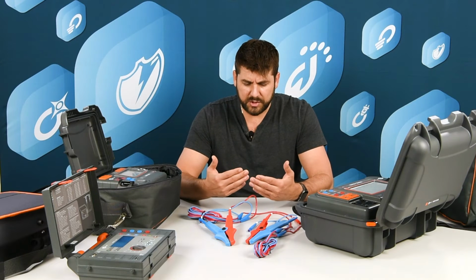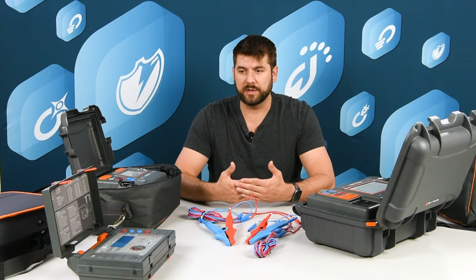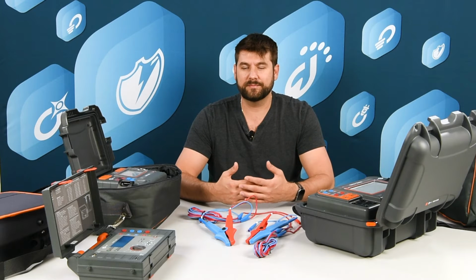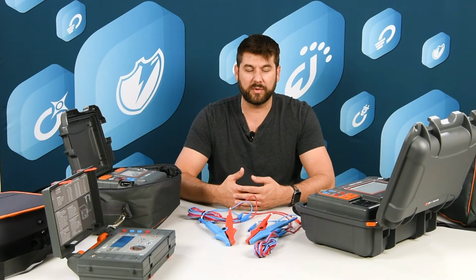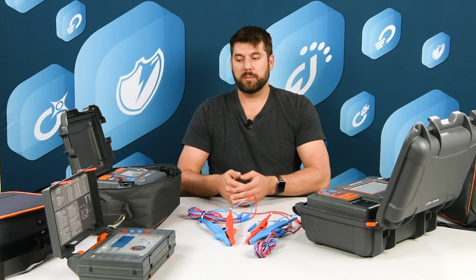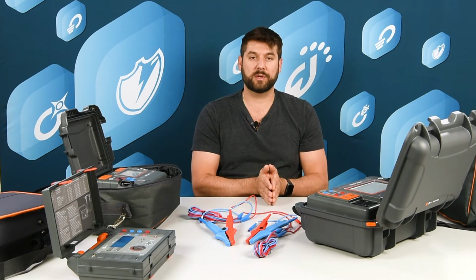Because some smaller connections that are only carrying a few amps may only need to have 500 microohms or 500 milliohms or, you know, 1,000 microohms. But when you get into higher capacity, higher current rated devices, an 800 amp breaker, 400 amp breaker, 2,000 amp breaker, you need to have microohm level resistance. You're talking about, you know, 10, 20, 30, 50, 100 microohms.